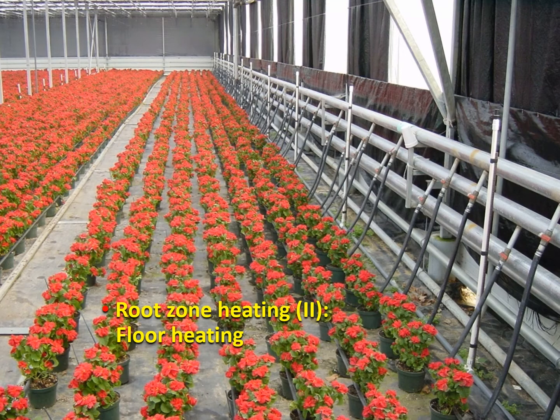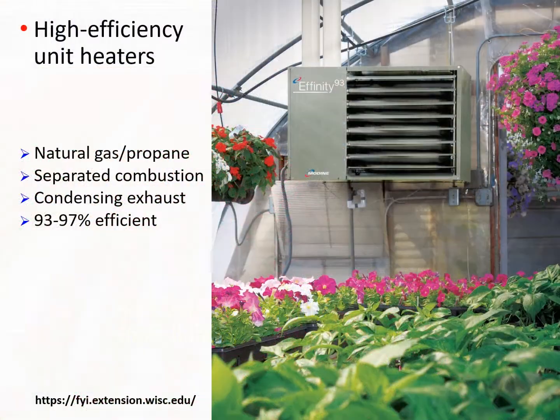While root zone heating systems are efficient, only moderately warm water temperatures can be used so as not to damage the plant roots. As a result, additional heating capacity in the form of perimeter and overhead heating pipes are needed to make sure that the greenhouse can be maintained at the set point temperature. High efficiency unit heaters can reduce the consumption of heating fuel. These high efficiencies are possible by recovering most of the heat contained in the exhaust gases as water vapor.